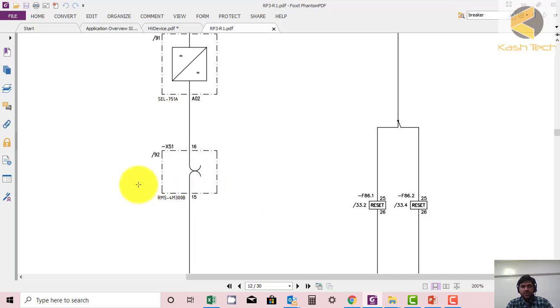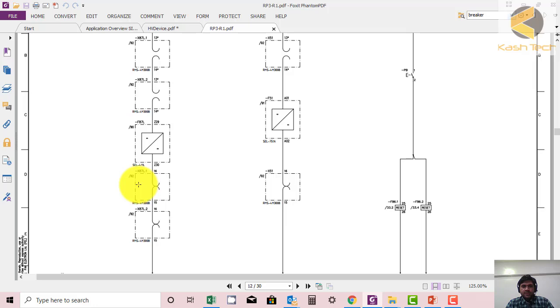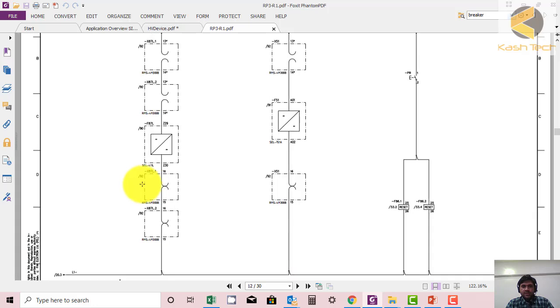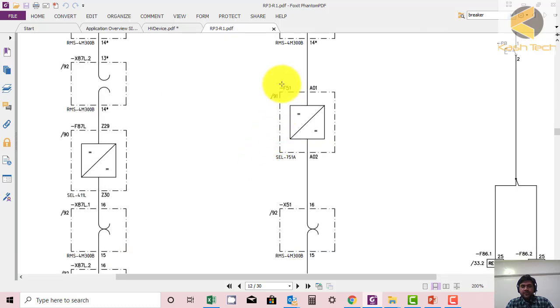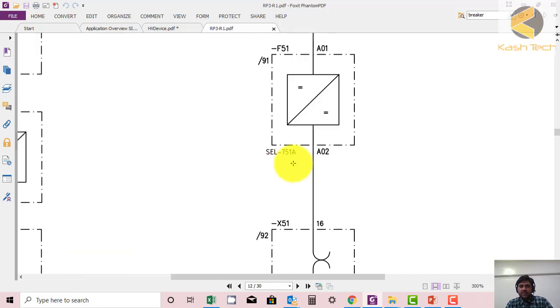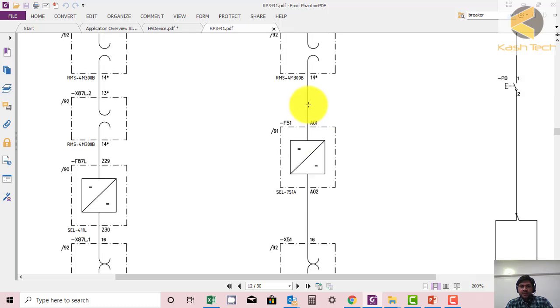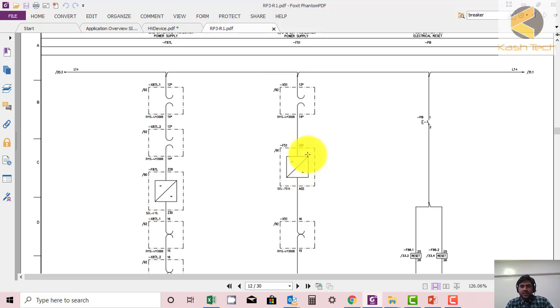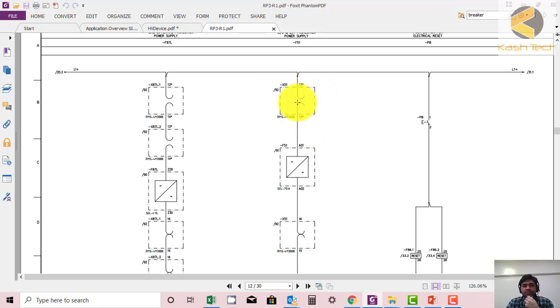This is the power supply of F51. 51 is the over current relay. F is the code for device. 51 is showing the function - function 51. The relay type here is SEL-751A. The supply is coming through terminal A01 of the relay, and its negative is coming to A02.